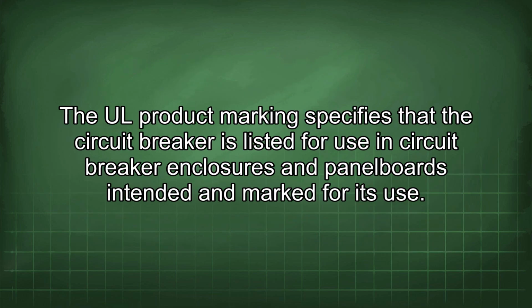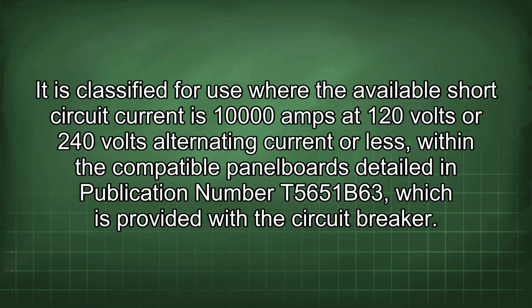The UL product markings specify that the circuit breaker is listed for use in circuit breaker enclosures and panel boards intended and marked for its use. It is classified for use where the available short circuit current is 10,000 amps at 120 volts or 240 volts alternating current or less, within the compatible panel boards detailed in publication number T5651B63, which is provided with the circuit breaker.